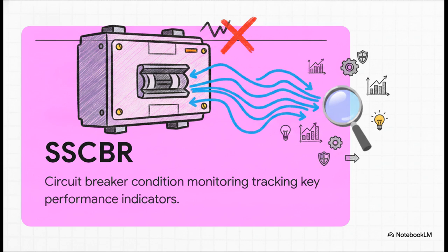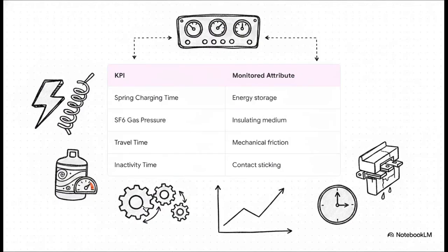We've talked a lot about motors and transformers, but we also have to consider the mechanical health of the circuit breakers themselves. Standard breaker failure protection is totally reactive, but SSCBR is completely proactive. It tracks key performance indicators to predict mechanical failure and catch degradation long before a catastrophic failure scenario ever gets the chance to occur. Think of these KPIs as your breaker's dashboard.